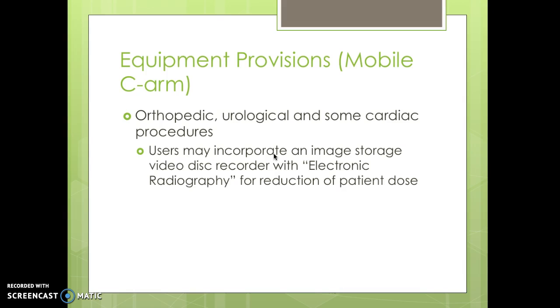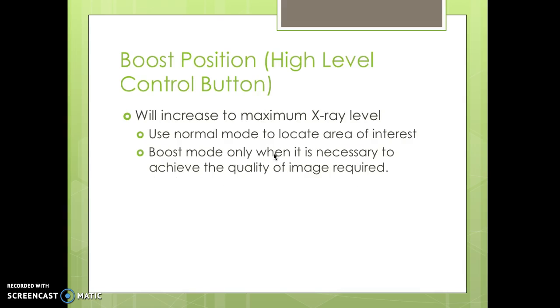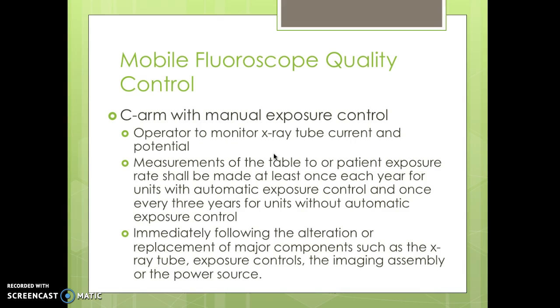For orthopedic, urology and some cardiac procedures, users may incorporate an image storage disc recorder with electronic radiography for reduction in patient dose. Boost will increase to maximum X-ray level. So use normal mode to locate the area of interest, and boost mode only when necessary to achieve the image quality that is required.